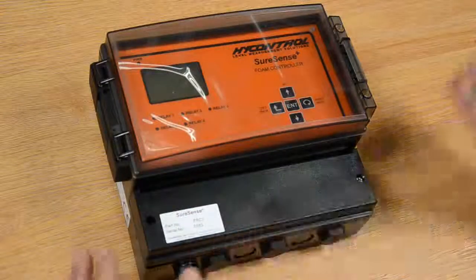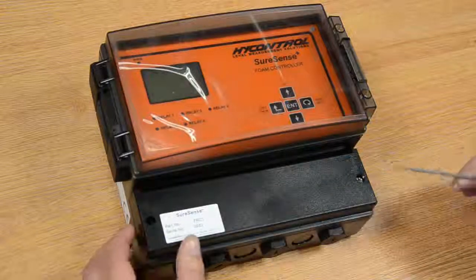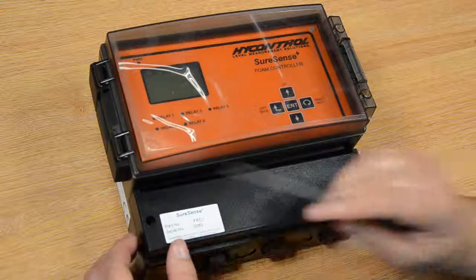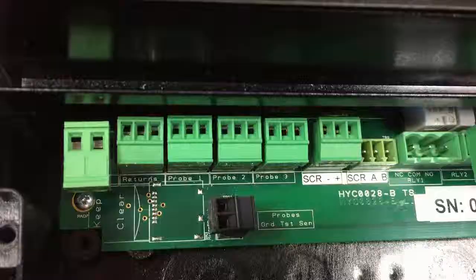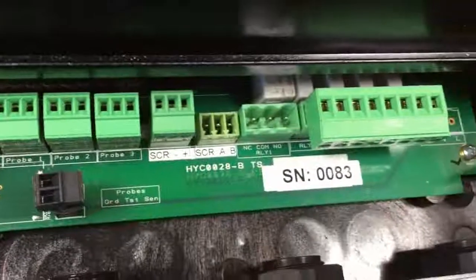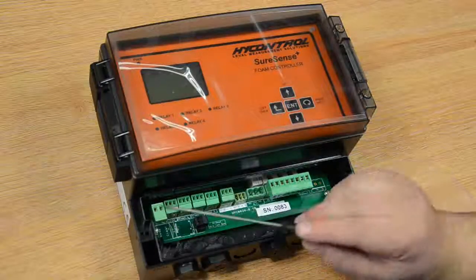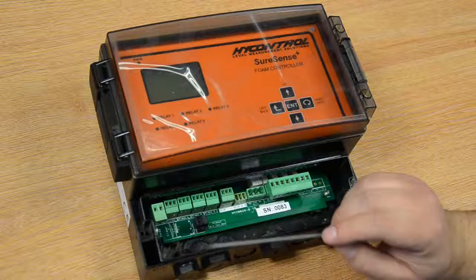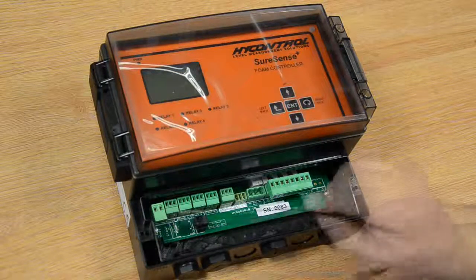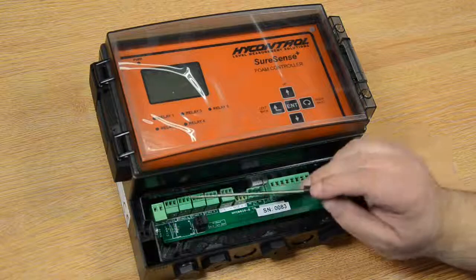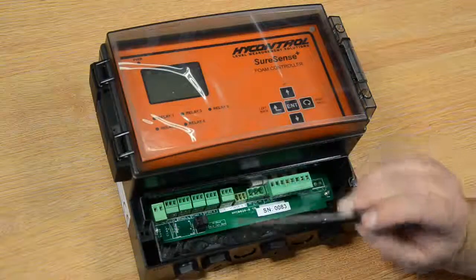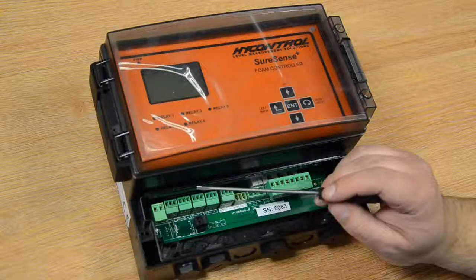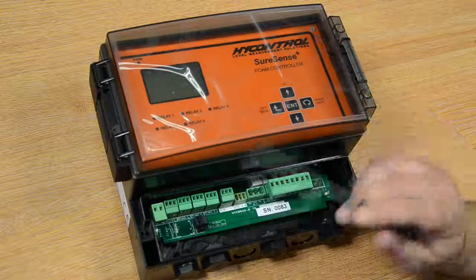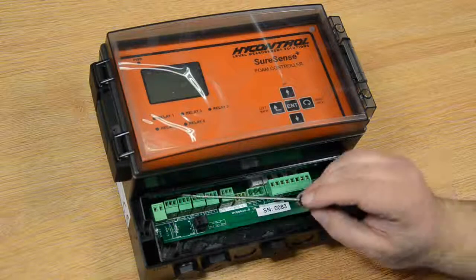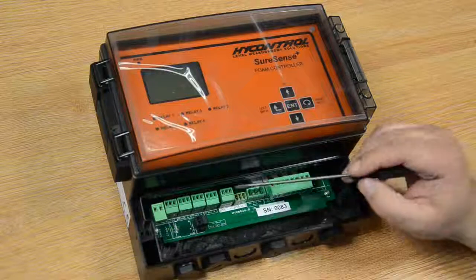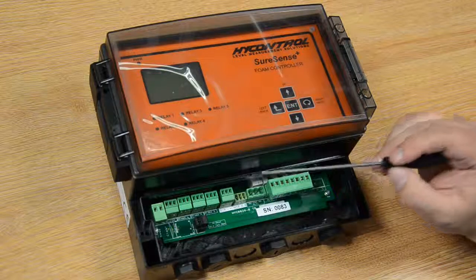Once you unbox your SureSense Plus, you'll need to remove the front cover. This is done by removing the two screws either side, and that will reveal the terminals. The terminals we've got here are the DC power. The unit is powered by 12 to 30 volt DC current, and then you've got your earth returns and probes 1, 2 and 3. On a single point probe you'll only need to wire in probe 1, on a double point probe 1 and 2, and on a 3 point, 1, 2 and 3. We also have the 4 to 20 milliamp output here.